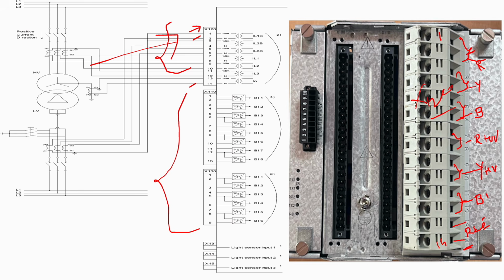Okay, so if we have a REF in our transformer, we can use these connections through a resistance and through a metrosil. The good thing is this relay you can utilize for 1 ampere and 5 ampere, friends. So you don't need to change the connections. You have to just make sure of it in your settings, at the time of settings, so you can change it over there. But for physical connection, you don't need to change anything.